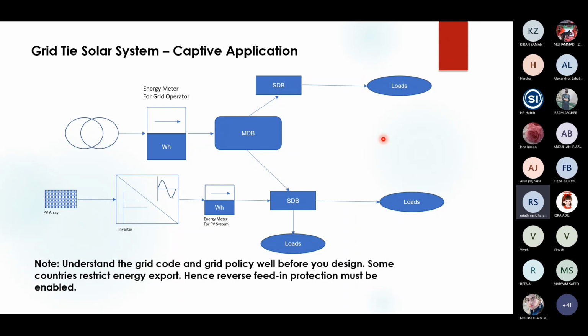But the most important thing is the country in which you're designing the PV system—first you need to know the grid code and grid policy, because in some countries feeding power back into the grid is forbidden due to their limitations and restrictions. So suppose the loads are very less, and I design such a system where the loads are very less...